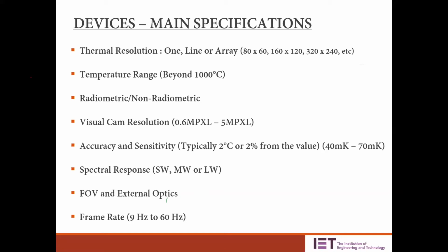also, radiometric versus non-radiometric is a really important parameter when you are trying to buy a camera. What it means is, say you are looking at an 80 by 60 sensor, you would have 4,800 individual thermal sensors measuring temperatures. So if you have a radiometric imager of 80 by 60, you would have 4,800 measurements in that photograph. But if your image is non-radiometric, you will only have that one spot you are trying to measure when the image is captured. If you are trying to measure another spot in the same frame, you would have to re-measure it. But with radiometric capabilities, once you capture the thermal image, you will have all the 4,800 readings in one picture.